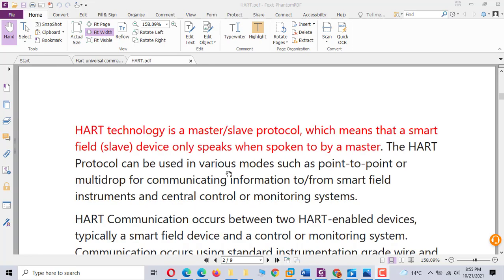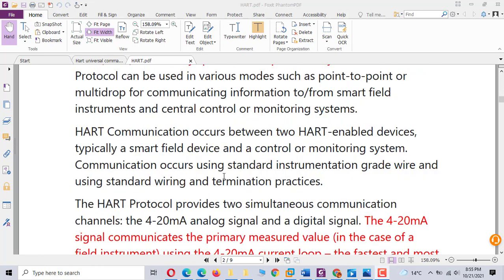HART communication is a master-slave protocol, the same as Modbus. The field device is a slave device, and the PLC, DCS system or PC is the master. The master just asks and requires, and the slave just responds. HART communication is between the smart field device and the control and monitoring system.